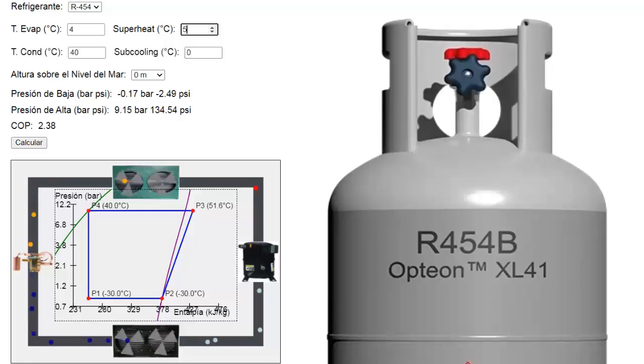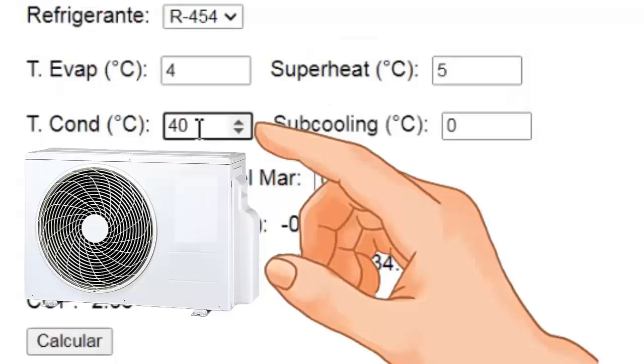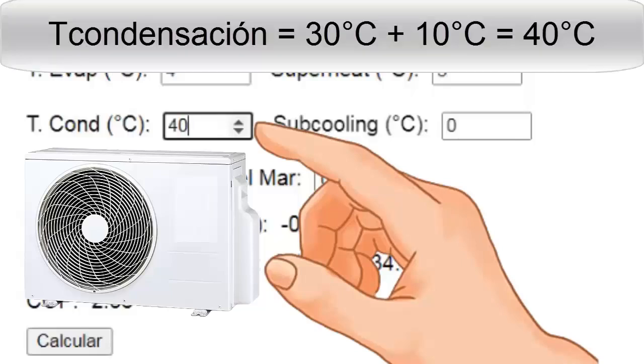Now let's focus on the condensation temperature within the air conditioning system. To calculate it, we add 10 degrees Celsius to the outdoor ambient temperature. For example, if the outdoor temperature is 30 degrees Celsius, the condensation temperature will be 40 degrees Celsius.